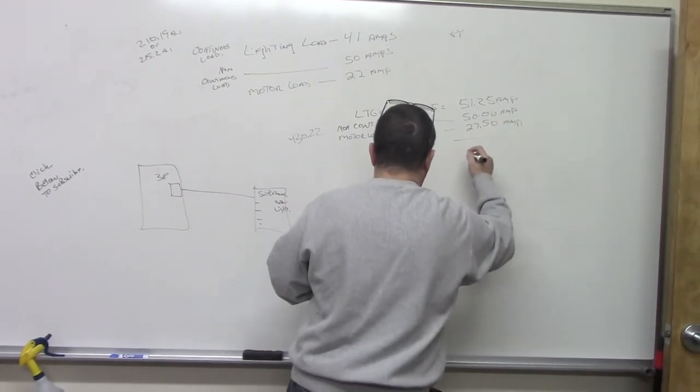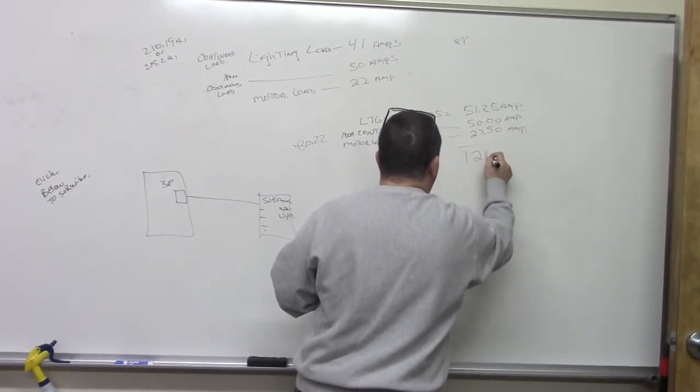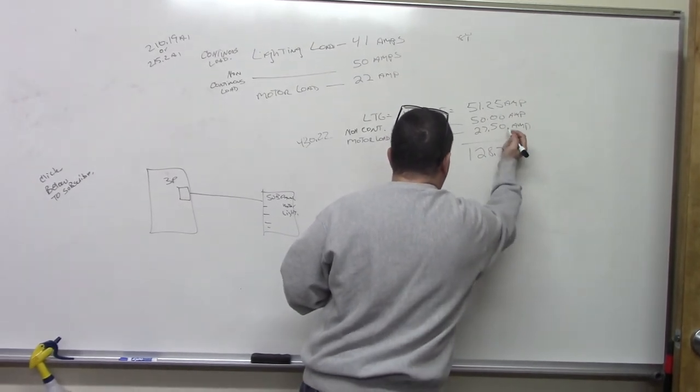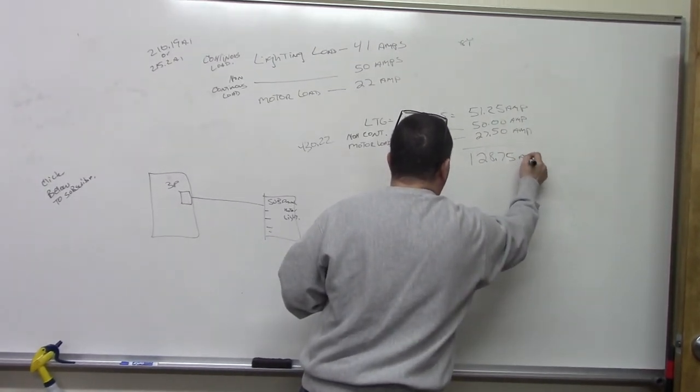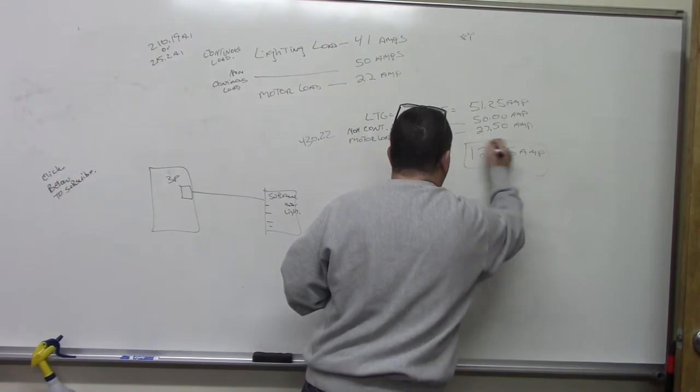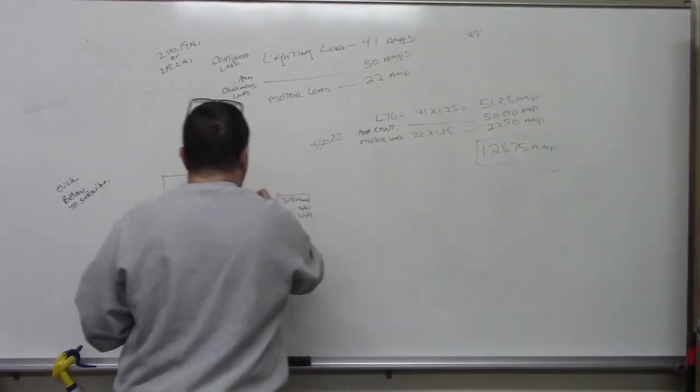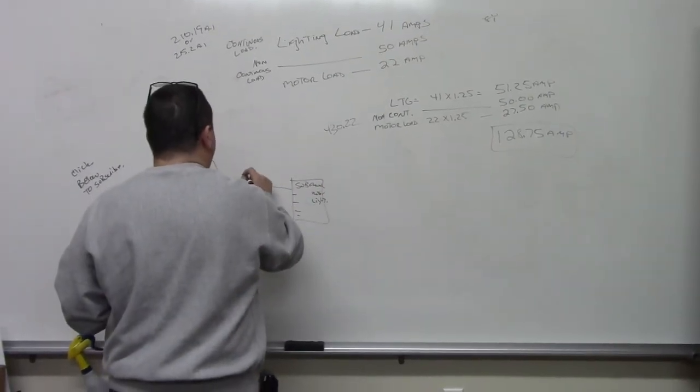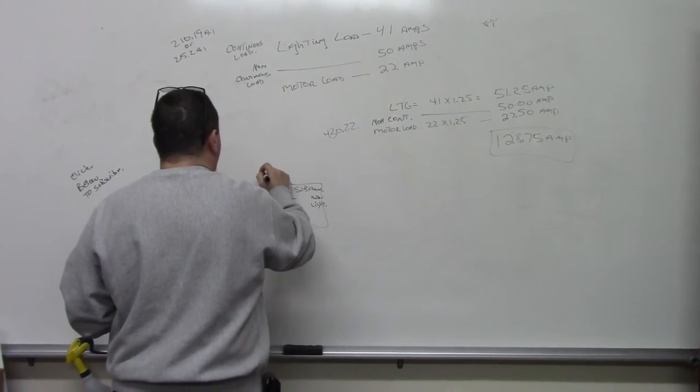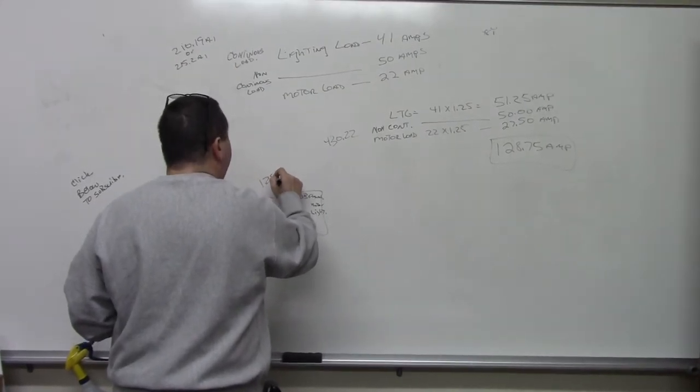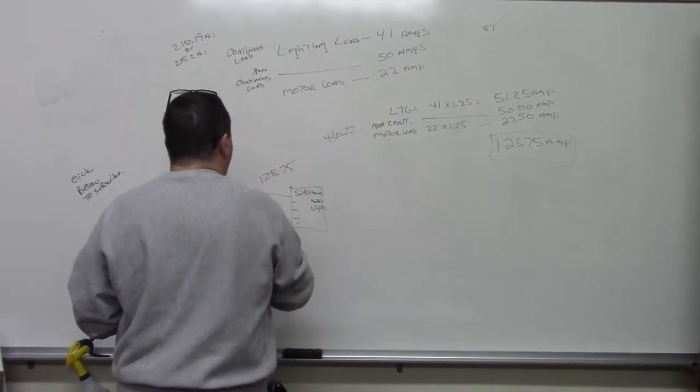And if we add it up, we come out with 128.75 amps. So this is my calculated load. So this feeder over here has to be at least 128.75.